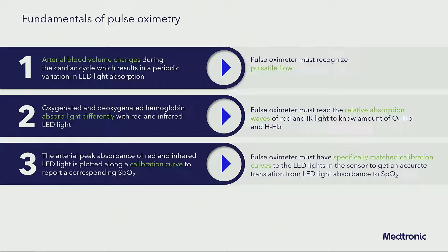Second key concept: oxygenated and deoxygenated hemoglobin absorb light differently at these different wavelengths. And the third point is that the SAT that you get, that lovely number, comes from a calibration curve that's unique to the sensor. It's unique to the part of the body that the pulse oximeter is placed on. So these are some of the key takeaways.